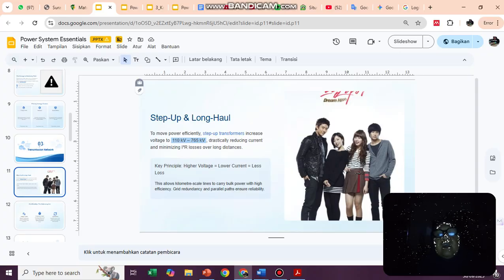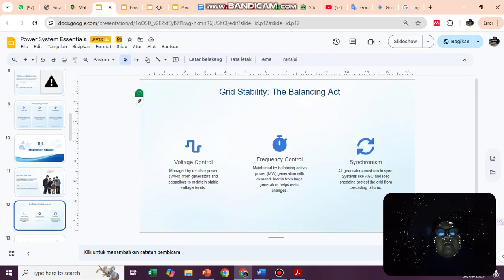Key principles: higher voltage means lower current and less loss. This allows kilometric scale lines to carry bulk power with high efficiency. Grid redundancy and parallel paths ensure reliability. And then voltage control, managed by reactive power from generators and capacitors to maintain stable voltage level. And then frequency control, maintained by balancing active power, megawatt generation, with demand. Inertia from large generators helps resist frequency change. And then synchronization. All generators must run in synchronization. Systems like AGC and load shedding protect the grid from cascading failure.